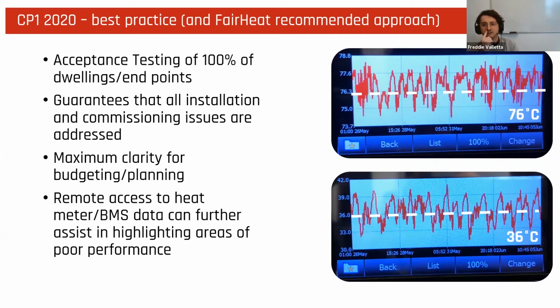Say, for example, these graphs on the right show return temperatures from 2 phases of a London development. The top graph shows return temperatures from the first phase, which didn't go through any testing at all. And the bottom graph shows the second phase where 100% of those dwellings were acceptance tested. And you can see there's a drastic difference between the return temperatures, showing that performance is actually being met in this phase.